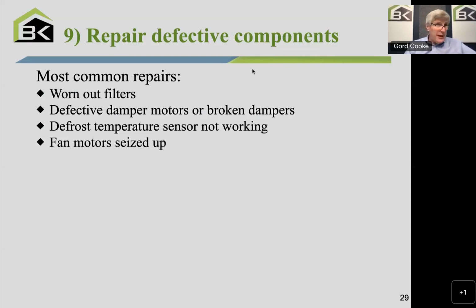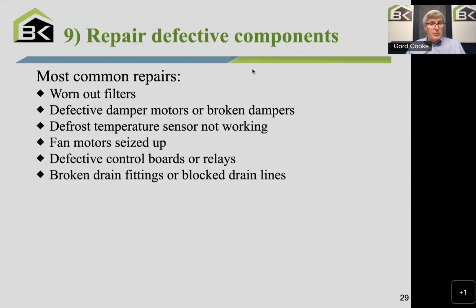After 15 years, my unit, it was 18 years, the motor seized up. Fan motors typically have a life of minimum 8 years, but maybe as much as 15 to 20 years. So you're going to have to change a fan motor from time to time. Typically they come as kits ordered from the manufacturer based on the model number, and it's typically plug and play, swap them out. Not that difficult to do. Sometimes defective control boards or relays, that's uncommon, because once control boards are working, they tend to work for decades. So it's not typically a problem. But maybe broken drain fittings or blocked drain lines, that's something to look for. Fairly common. Maybe kids are playing in the basement or something, and the drain fitting gets knocked or broken. So we have to think about that.